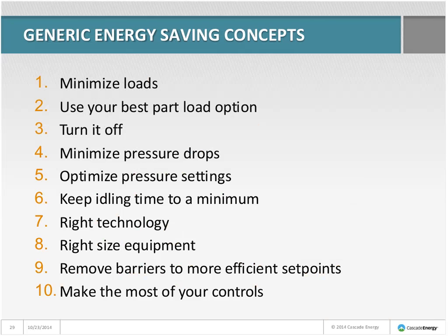With the textile plant, what did these guys do? Minimize loads — the leak load was a real big hitter. In this case the flow controller wasn't benefiting them, so removing it and letting the variable-speed compressor control the pressure saved energy and allowed them to optimize pressure settings. Those were the key concepts in play.